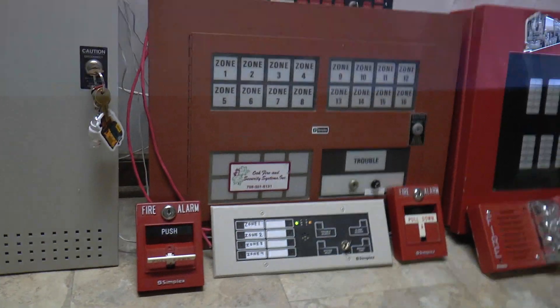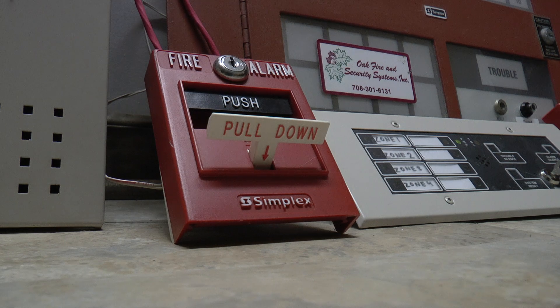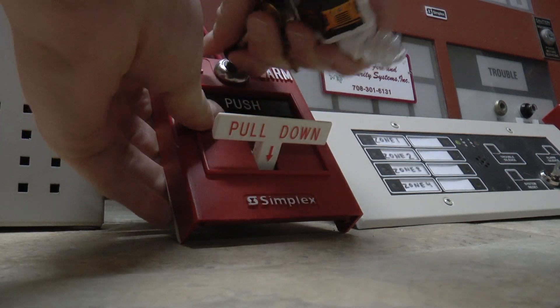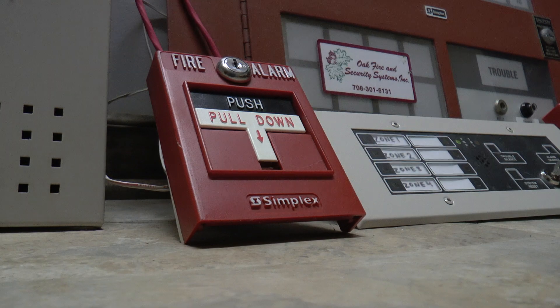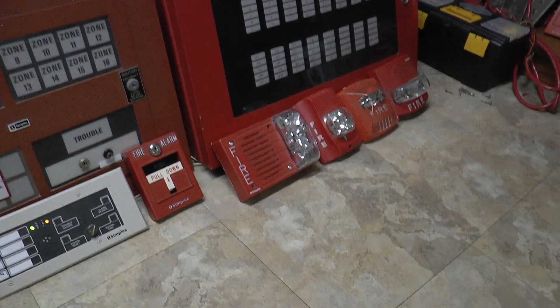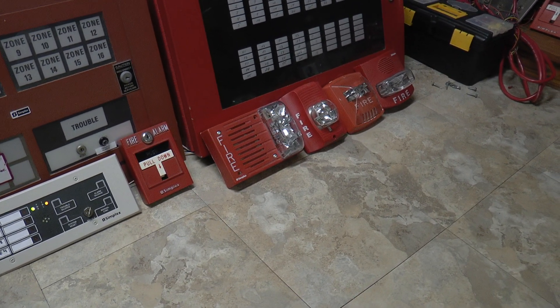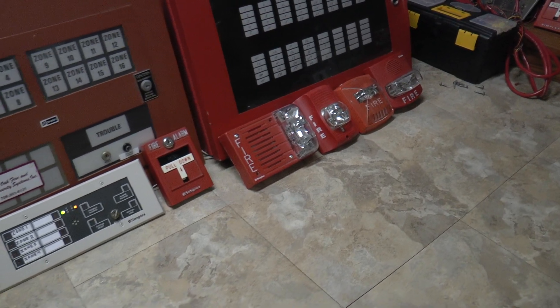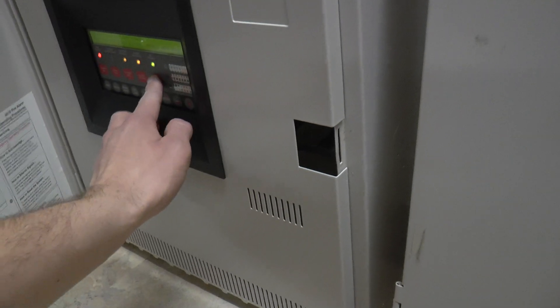All right, that was painfully loud. That alarm sounds very much like the TrueAlerts — in fact I think I said this in one of my other videos, I think the 9252 actually has a TrueAlert horn in it. It is a four-wire horn strobe but the jumper has not been cut, so it's still set up as a two-wire horn strobe. I'll put a reset in the 4010.